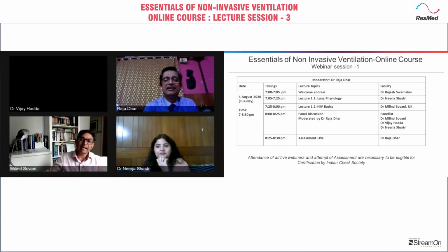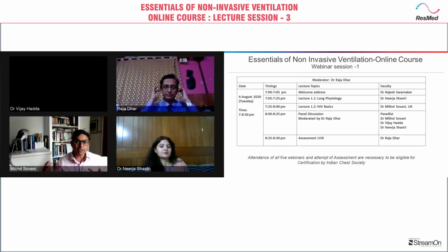Yeah, sorry. So the helmet is really good from the pressure sore point of view, but because of the big dead space, triggering can be a problem. Similarly, you are likely to need much higher flows, and the ventilator needs to have a much bigger pump to cope with that. So we just need to be aware of one thing offsetting the other.